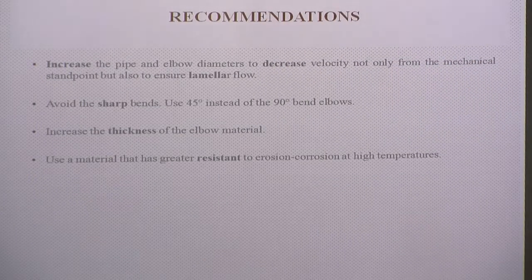The recommendations are, you can increase the pipe and elbow diameter to reduce velocity, not only from a mechanical standpoint, but to ensure laminar flow, free flow of gas. They avoid sharp bends by using 45 degree elbows instead of 90 degree elbows. They increase the thickness of the elbow material, and they can use a material that has a greater resistance to corrosion at high temperatures.